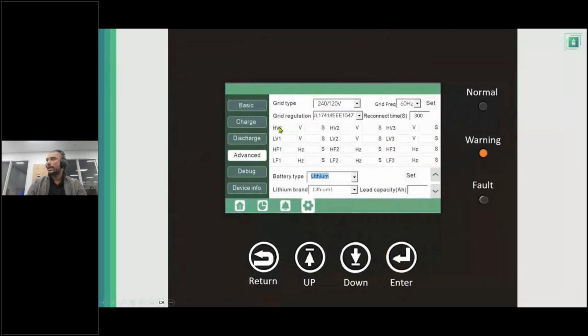And then after that, I'm going to select the grid type and the frequency, and make sure you select set for every change you make, right? And then I'm going to select the grid regulation. Now, I would do all three of these at the same time and then click set, because essentially if you change the grid type, frequency, or grid regulation, it will reboot, because then the system has to convert into what voltage it is, what the grid regulation is, or what the frequency is, right? So make these changes at the same time, so 120, right, or 208, depending on what your application is.